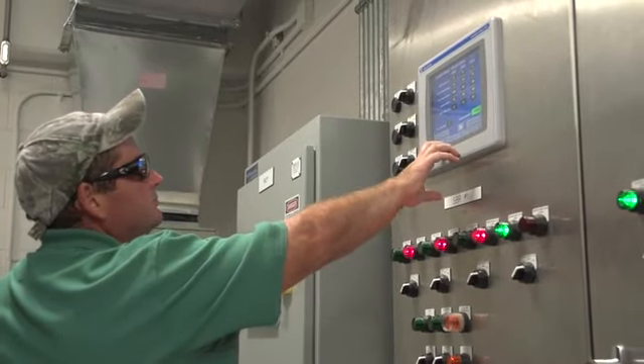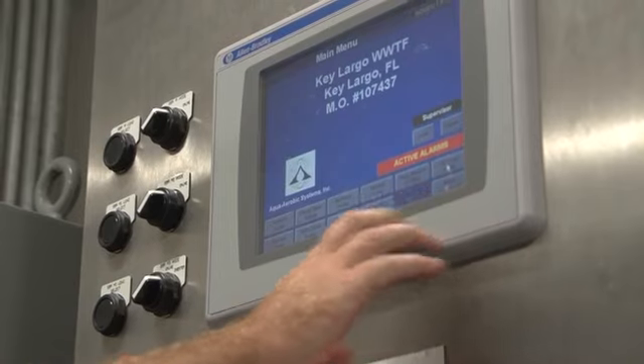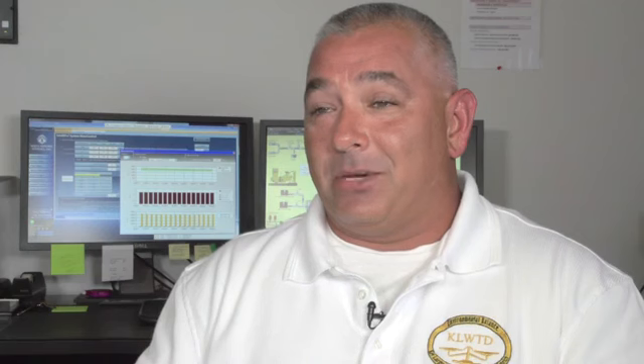By integrating Aqua-Aerobic Systems' Intellipro Monitoring and Control System, Key Largo is able to optimize its plant operations by improving efficiencies, cutting costs, and reducing energy consumption. When running a plant, being able to monitor minute-to-minute, second-to-second, hour-to-hour is great. It helps you know when to sample, when to add air, when not to add air, whether we're achieving anaerobic or aerobic conditions. The beautiful thing about the DO control is that we've seen a cost savings of up to $10,000 a month in the last year after dialing in the air with regard to time and DO set point.